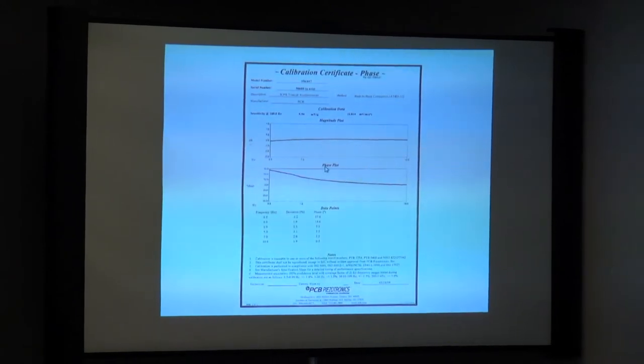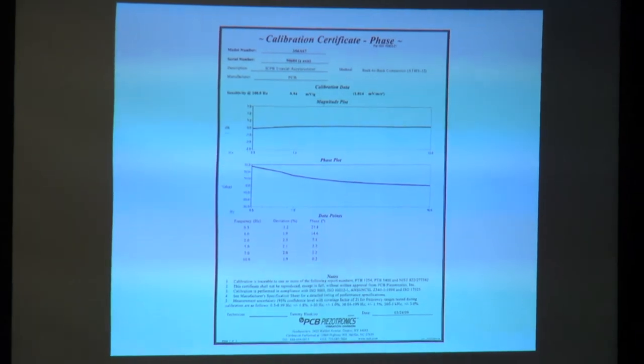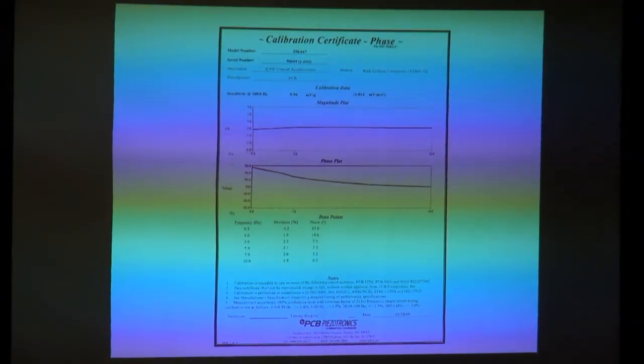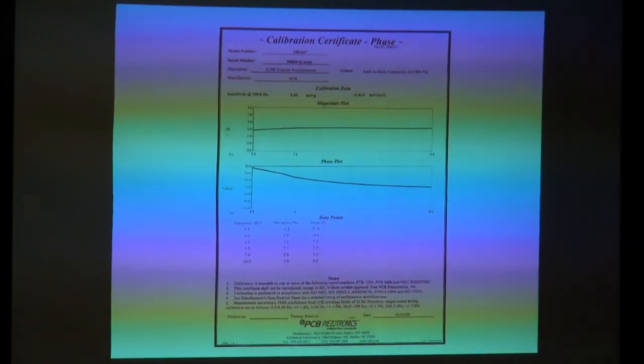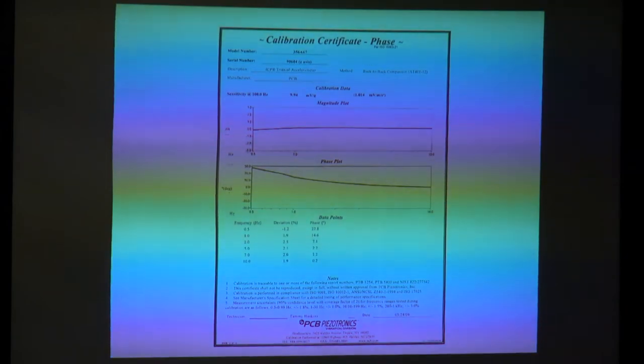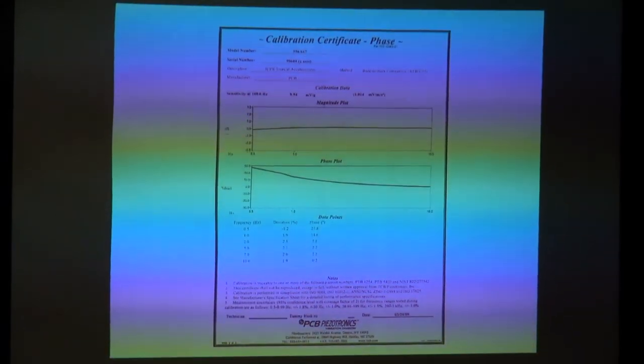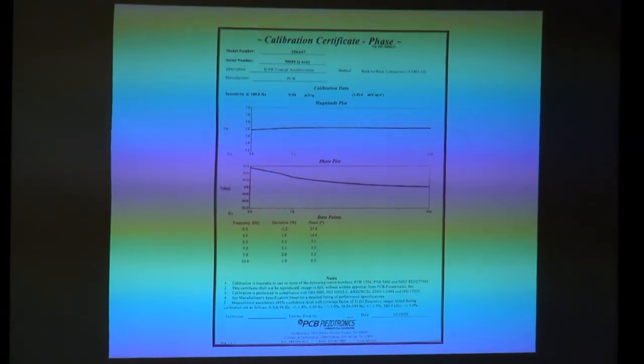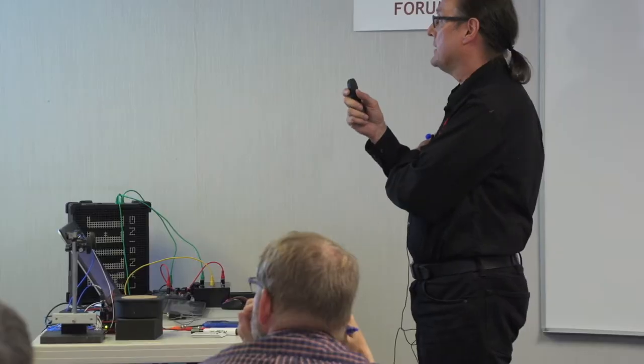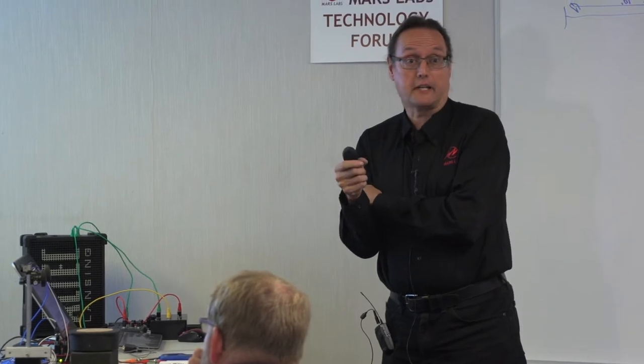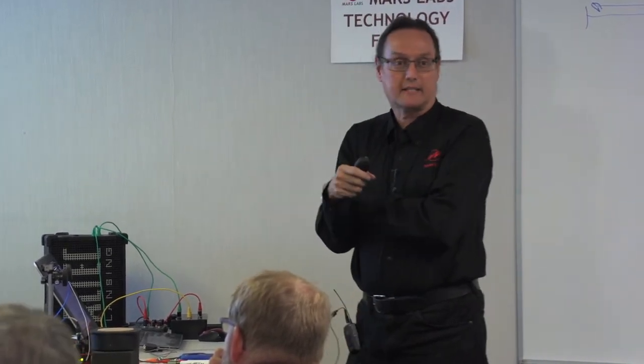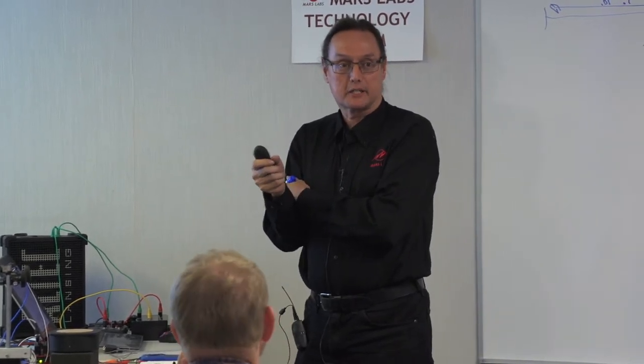A lot of cal data sheets look like the one PCB gave me — still in dB, with amplitude pretty tight and a phase plot included. Most ICP accelerometers give you cal data down to about 10 Hz. If you're going to use it below 10 Hz, you have to ask yourself: is it good data? If someone asks what it's doing at 5 Hz, 3 Hz, or 1 Hz — the answer is you have an idea but the cal sheet only goes to 10 Hz. If you're per ISO 17025 and need to show data, that's no good.